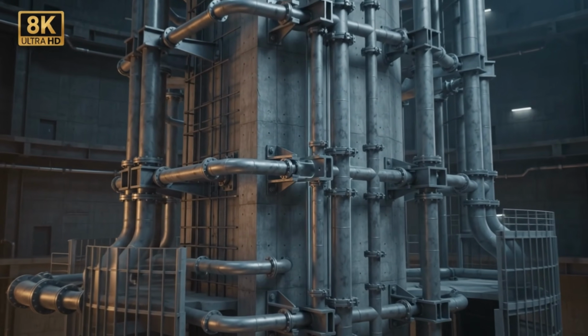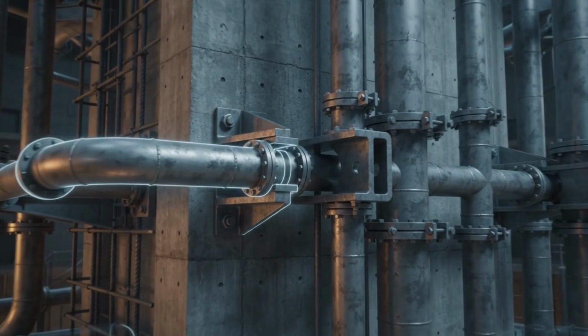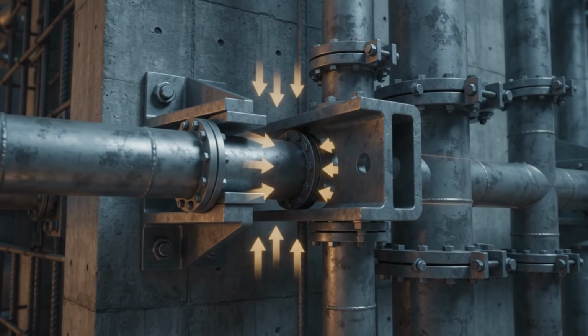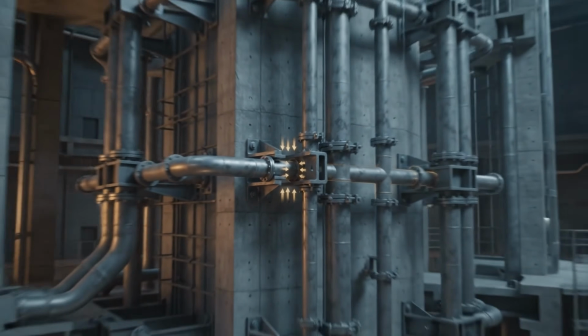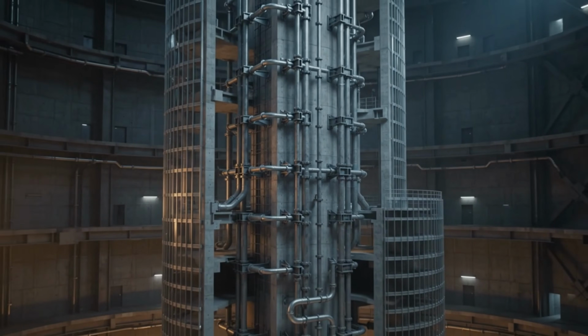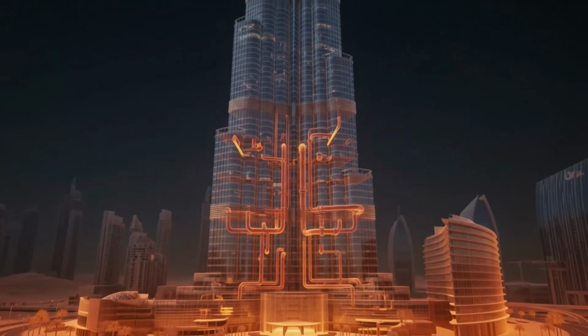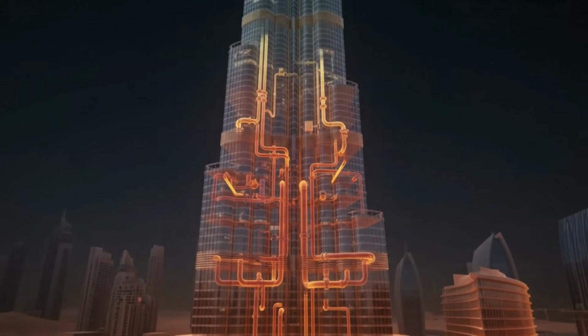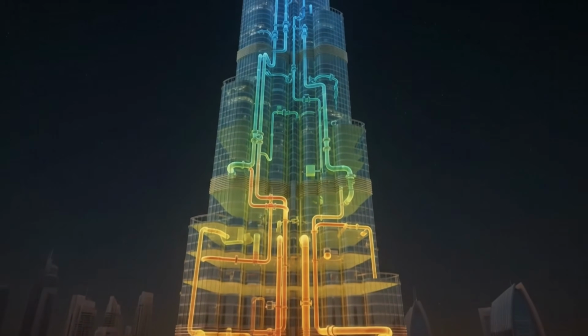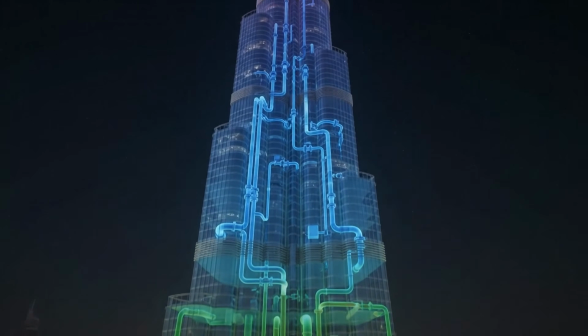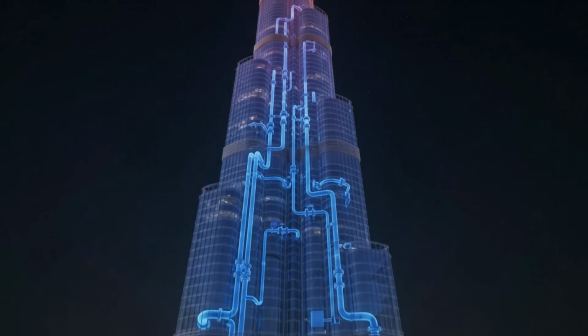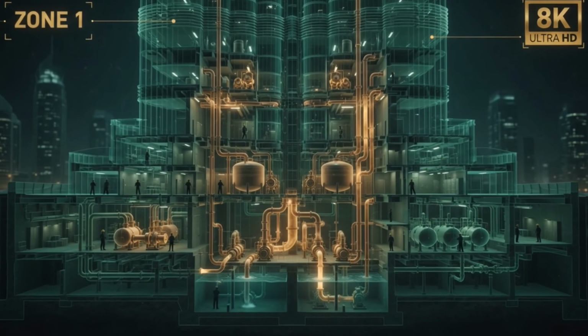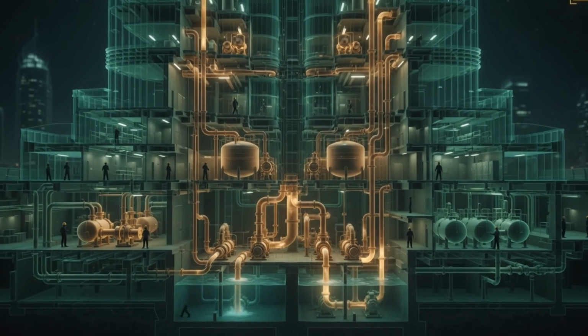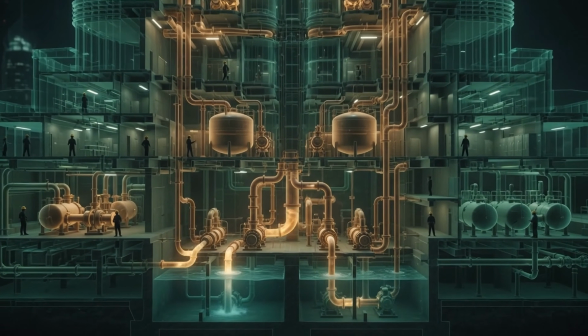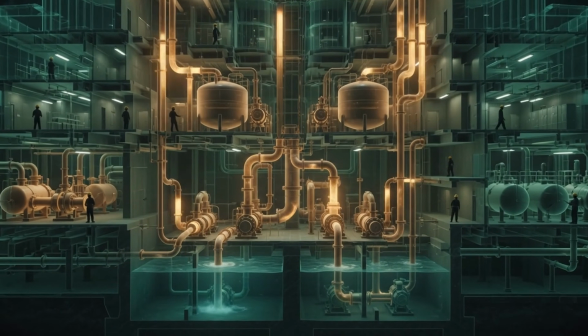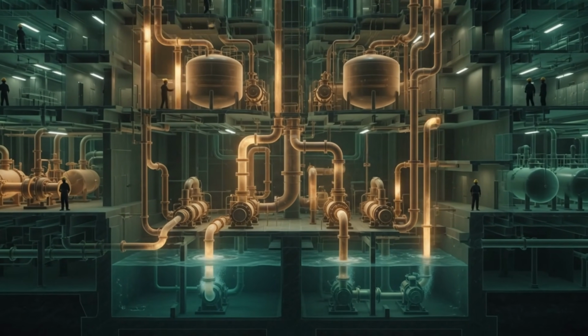Pipe guides anchor the system to the building's structural core while allowing thermal expansion. Because temperatures inside a skyscraper can change dramatically from basement to summit. From the scorching 50 degrees Celsius desert heat at street level to near freezing temperatures at the summit, the pipe system must handle over 60 degrees of temperature differential. Zone 1 handles the lower 45 floors, the residential lobby levels and commercial spaces. Its pumps move water from the reservoirs.